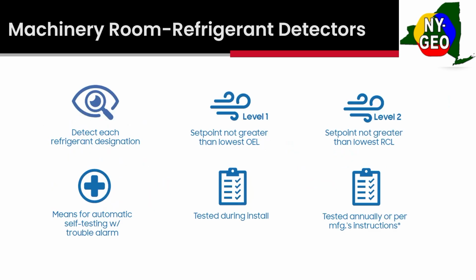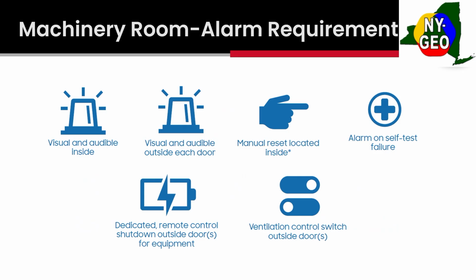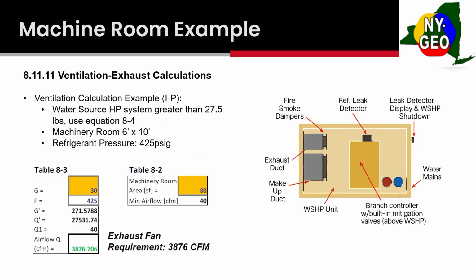So here's more of the requirements. You've got your set point requirements here. The big thing is automatic self-testing and annual and monthly inspections of your refrigerant detectors. Another thing is alarms. Not only do you need a visual alarm inside, you need one outside as well, and a manual reset inside. So those are two big things different from previous versions of the machinery room. So let's talk about the ventilation.